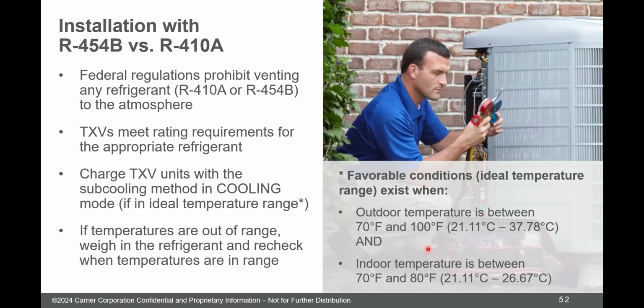If it's an inverter, most manufacturers of inverters for 410A or 454B or R32 want the contractor to weigh the charge in. That's the normal way to do it. Weigh it in. If your line set's longer than the book says, it'll tell you how much math you've got to do to figure out how much extra to weigh in, right? That's what we normally do for an inverter.